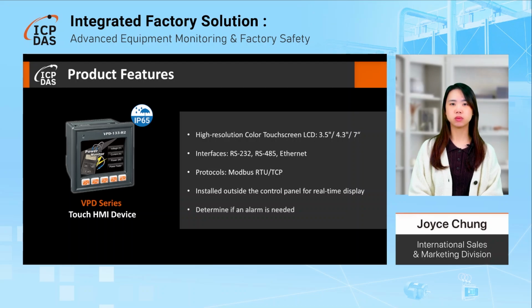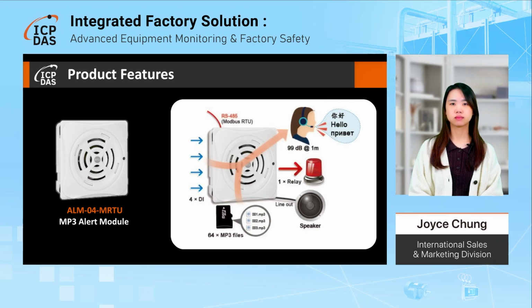In this case, the VPD module is installed outside the control panel to display the real-time vibration data, including peak-to-peak acceleration and RMS velocity. Also, the VPD module uses the threshold values to determine if an alarm should be triggered. The ALM04 MRTU MP3 alert module features 4 isolated digital input channels, 1 relay output channel, 1 MP3 audio line output, and 8 alarm modes. Also, it includes a built-in micro SD card for storing up to 64 pre-recorded audio files.